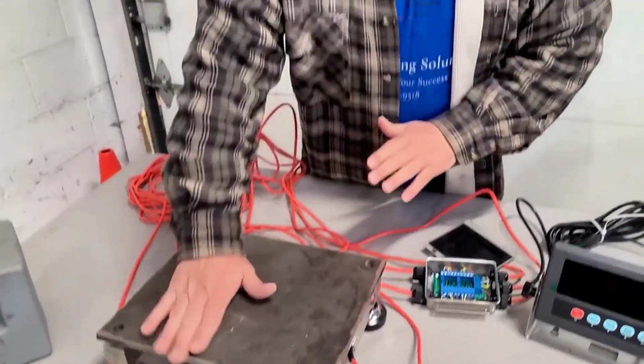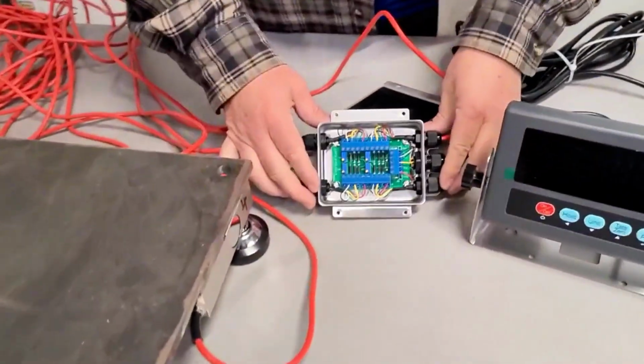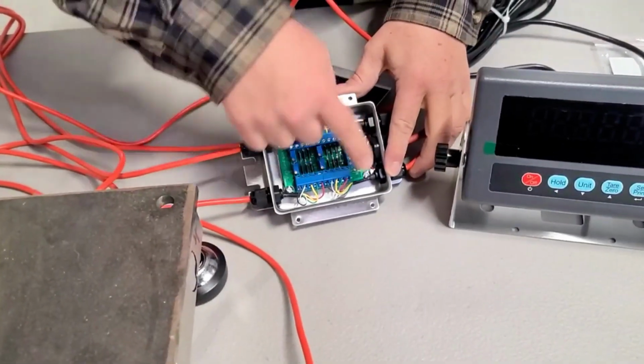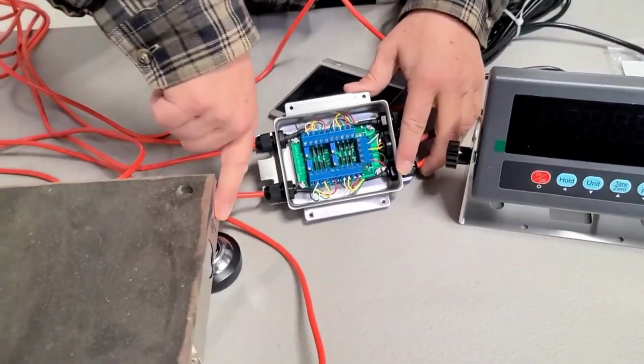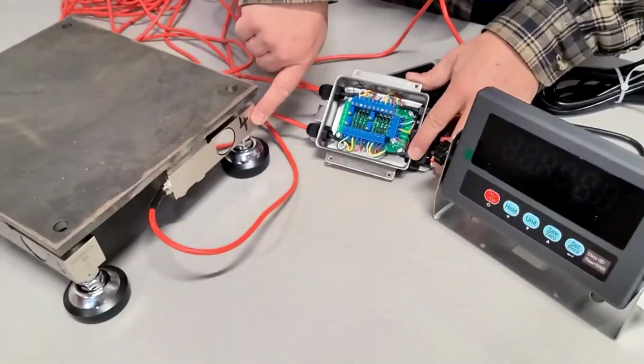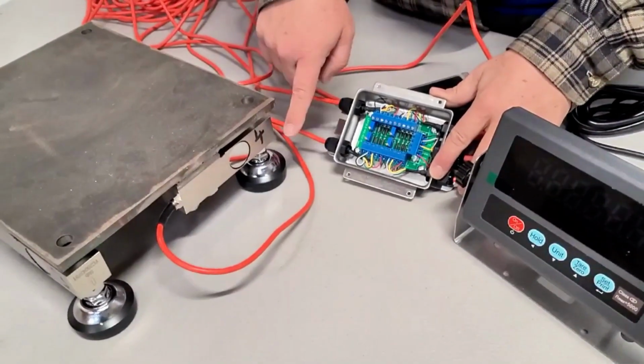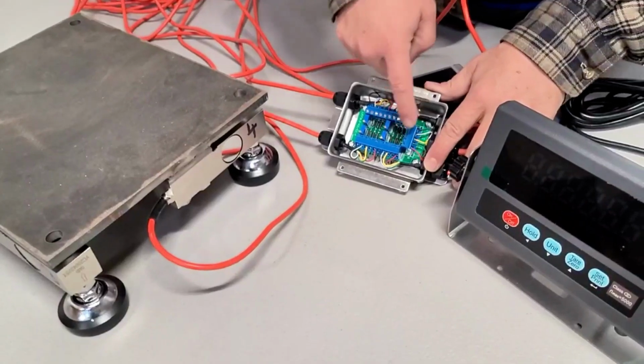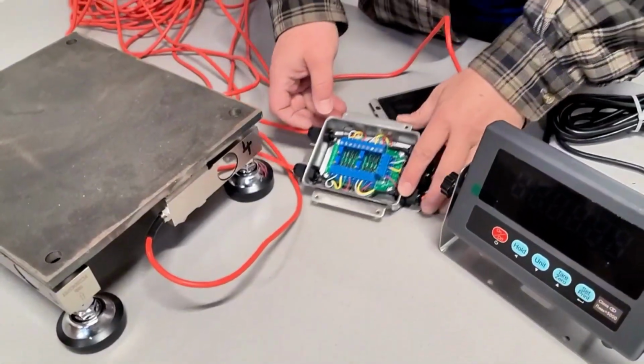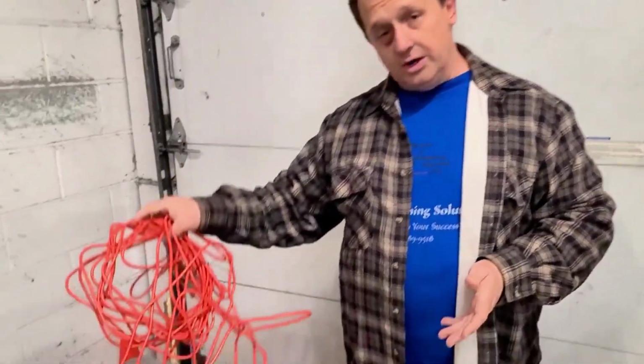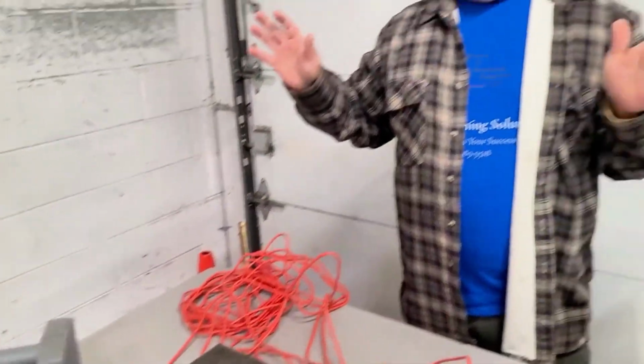Now, when you wire the summing box, in this instance, each and every summing box has all the load cells wired in. Now, as you can see, I actually numbered the load cells. Reason for that is because I'm actually using number 4 on a number 4 terminal. That's also explained on the card itself. Now, every single load cell comes with 3 meters of cable, so it's a pretty long distance that you can actually run the cable with. Now, I always recommend, if you use this outside, to run the cables into conduit and then put it into the summing box.